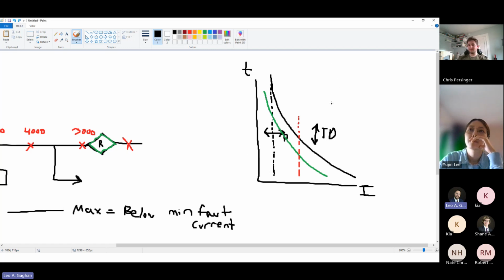A pretty good rule of thumb: fuses usually best fit an extremely inverse curve. It's just the nature of how they're built. Reclosers, which often need to coordinate with fuses, will use curves that best fit an extremely inverse. And sometimes you would want a very inverse. That's usually a more typical setting that you would see in a transmission system.